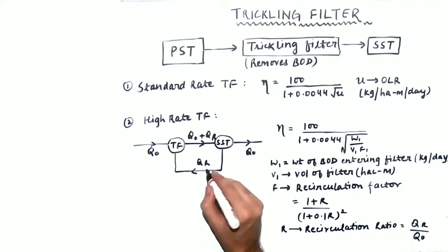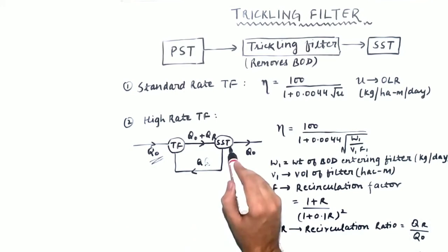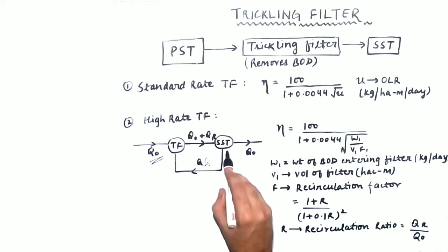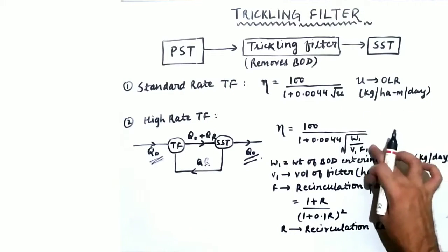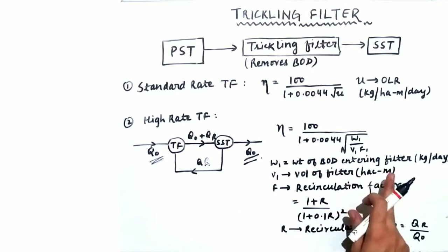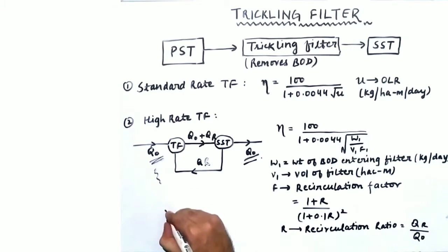In the high rate trickling filter, the recirculation flow QR comes from the secondary sedimentation tank back to the trickling filter. So the trickling filter receives Q0 plus QR, and the secondary sedimentation tank releases the original Q0 discharge. The efficiency is calculated by the formula E = 100 / (1 + 0.0044 × √(W1 / V1F1)), where W1 is the weight of BOD entering the filter in kilogram per day, V1 is the volume, and F1 is the recirculation factor.